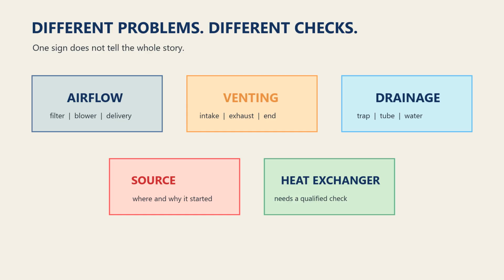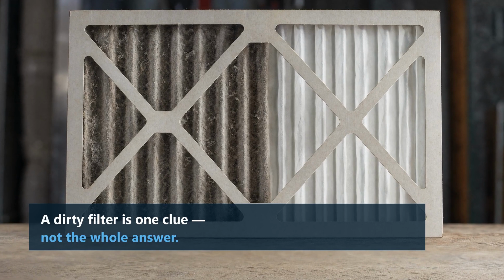A plugged filter can reduce airflow and contribute to limit control operation, but it does not prove that a heat exchanger needs cleaning. That is why proper service begins with diagnosis.